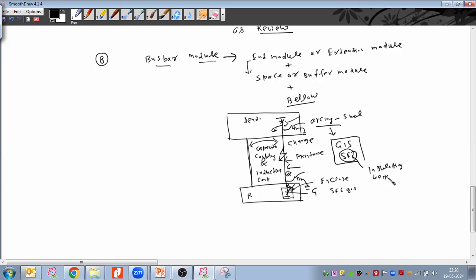So what we want when we are closing this line earthing switch is a very fast closing, very quick closing, very high speed closing, so that we can reduce the arcing time. If closing is fast, we can reduce arcing, right? Now your contact will be quickly created, right? Yes, sir.